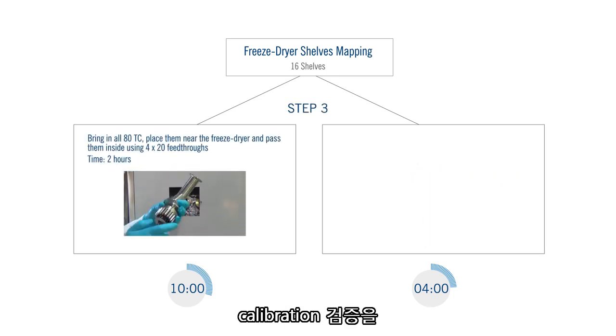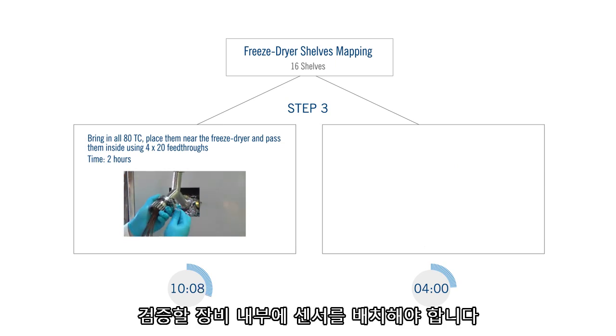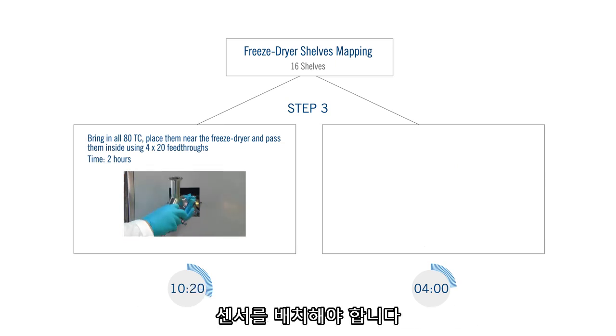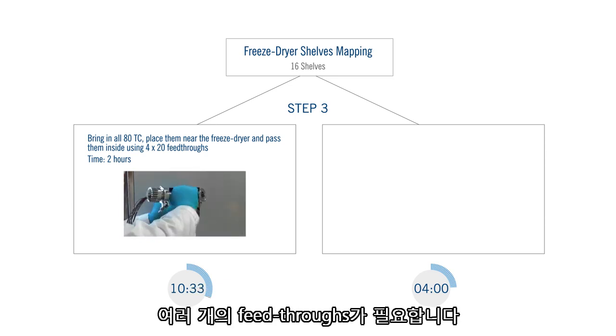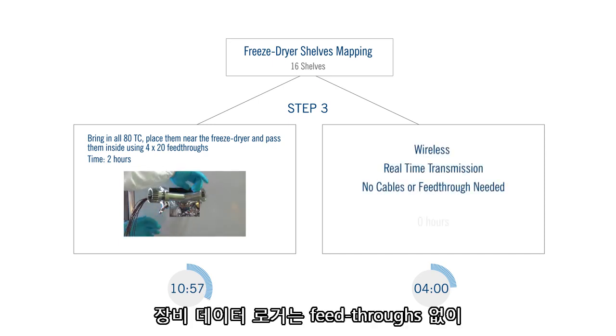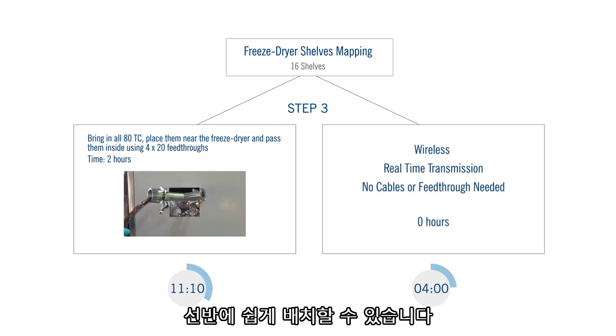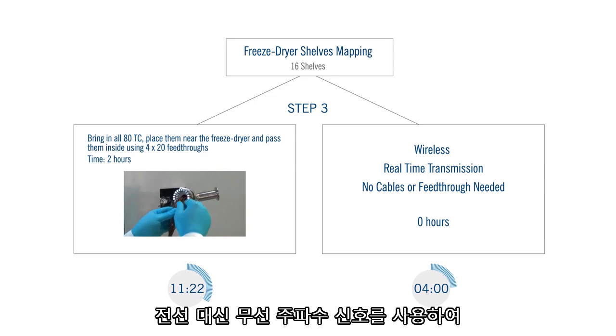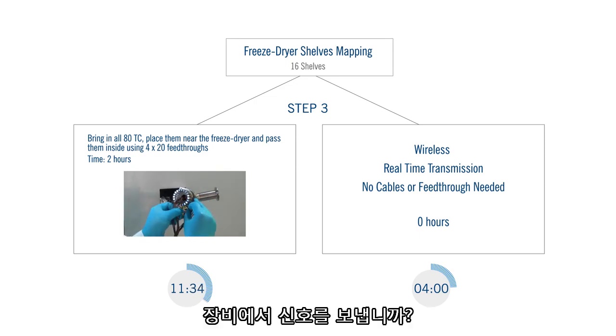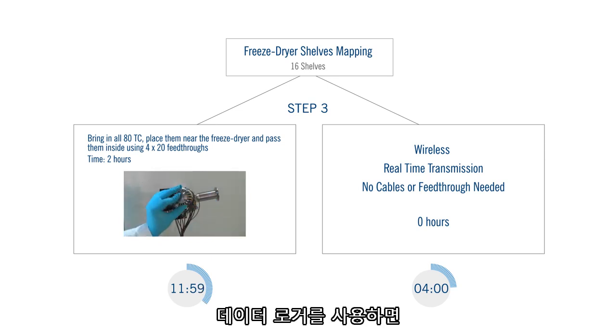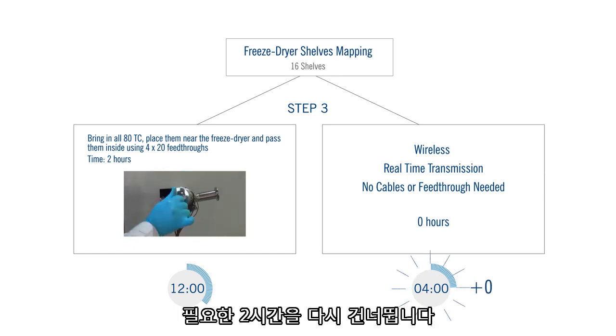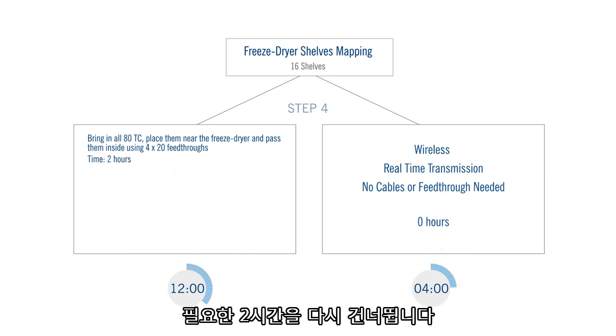Once the calibration verification of the sensors has been performed, the sensors have to be placed inside the equipment to be validated. Several feed-throughs are required to pass all the thermocouples inside the equipment. Data loggers are easily placed on the shelves without needing a feed-through. Remember, they send the signal out from the equipment using radio frequency signal instead of wires. The 2 hours needed to pass the thermocouples inside the freeze dryer are once again skipped when using data loggers.